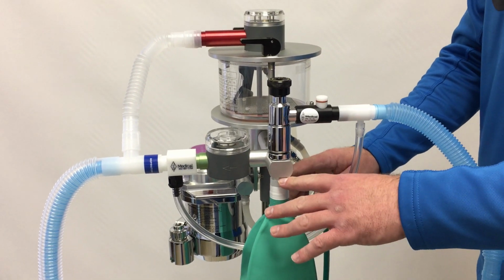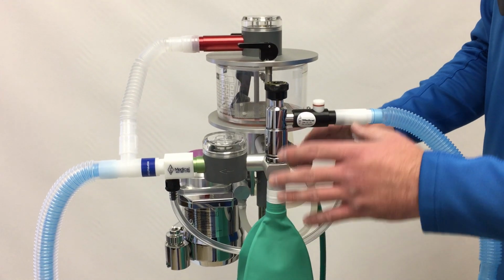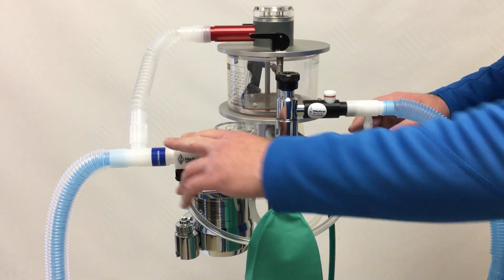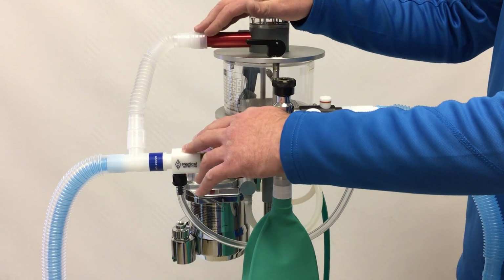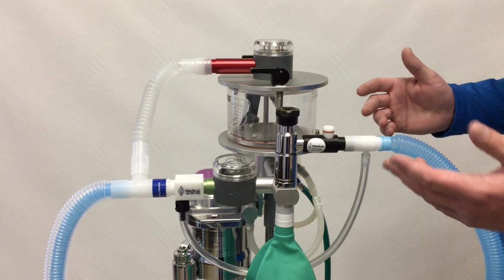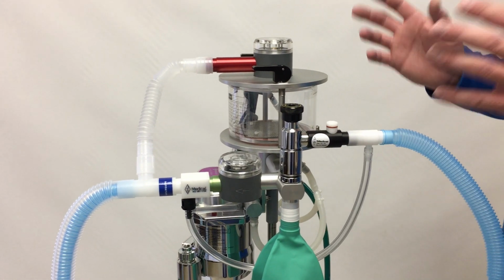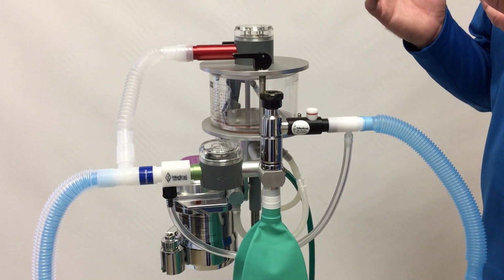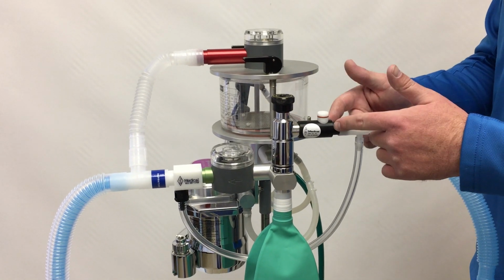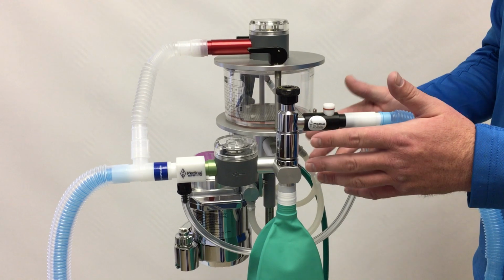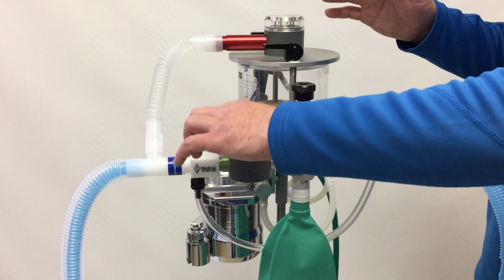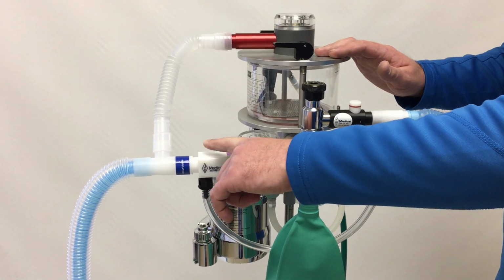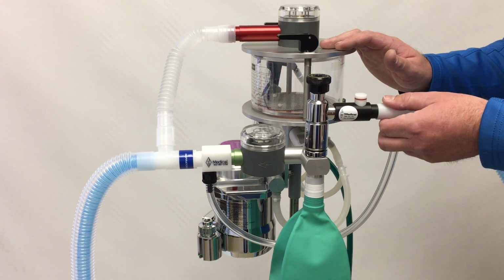In certain circumstances, you could even connect it to the bag. We don't recommend doing that because it's a little bit out of sight. It's good to be able to see that. So one of the circuit connections is preferred, but on some older or some strange anesthesia machines that may or may not be out there, it may be beneficial to connect it to another spot. But the valve needs to be connected to the patient's circuit and the exhaust to the exhaust.